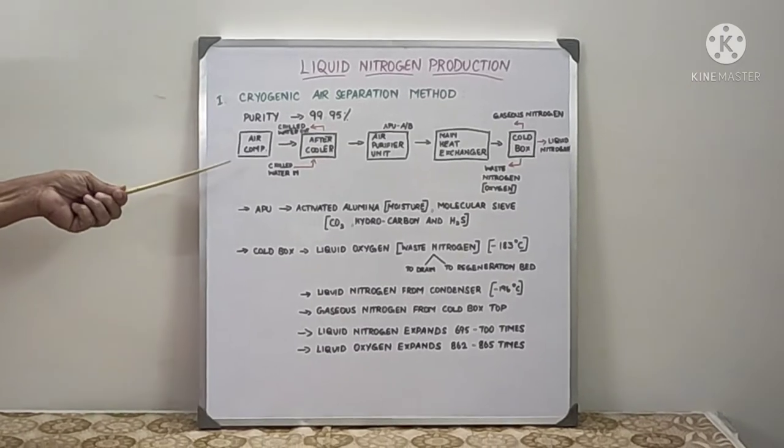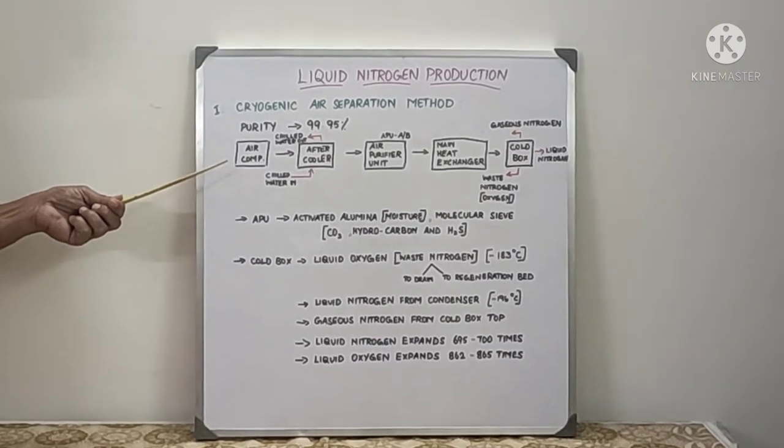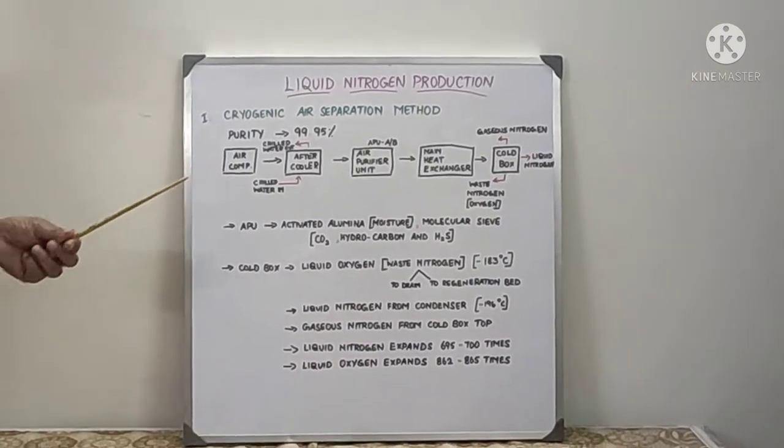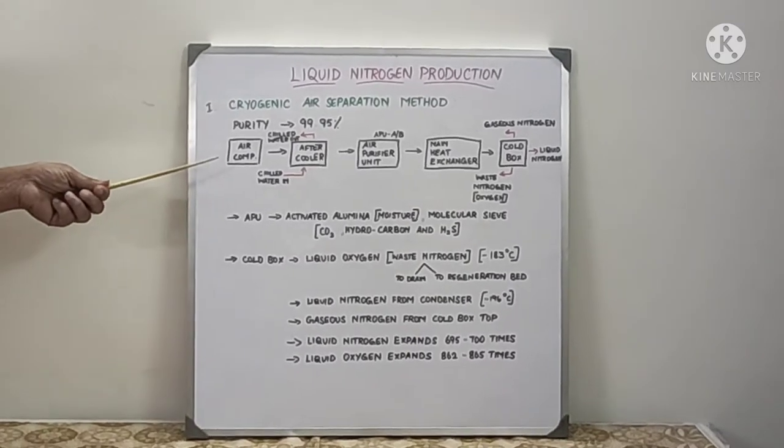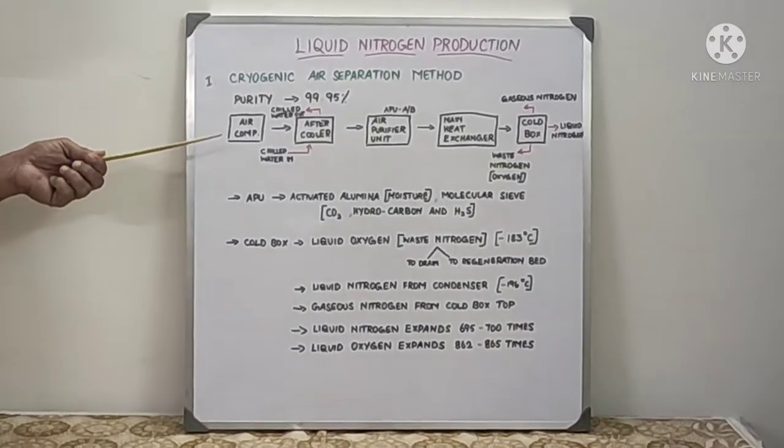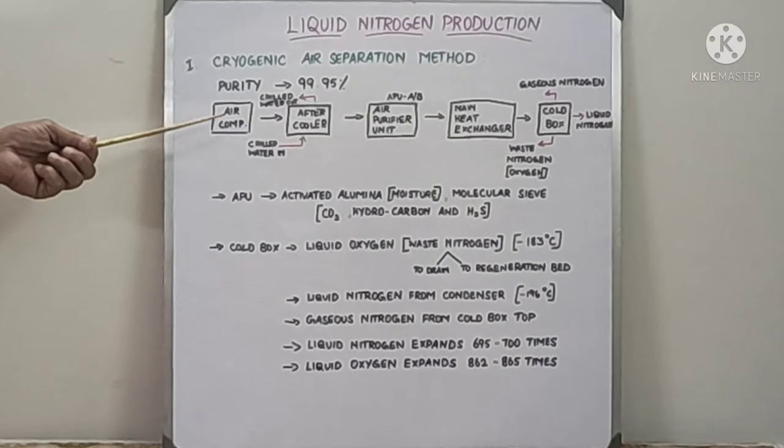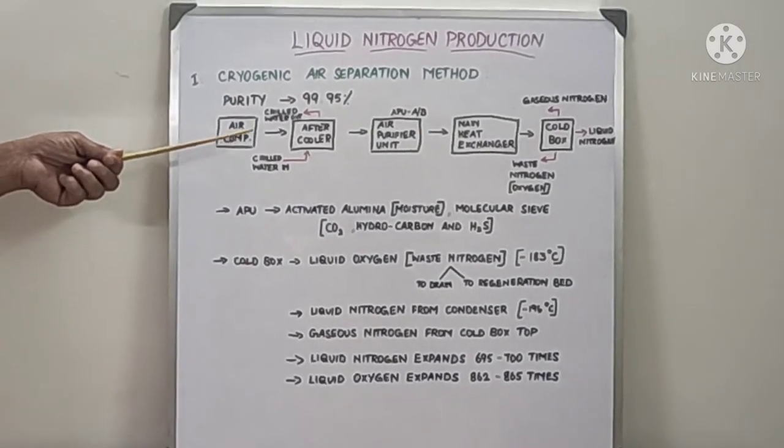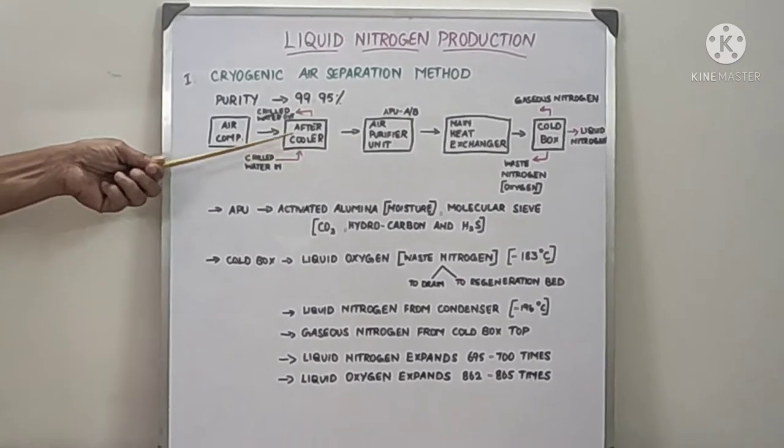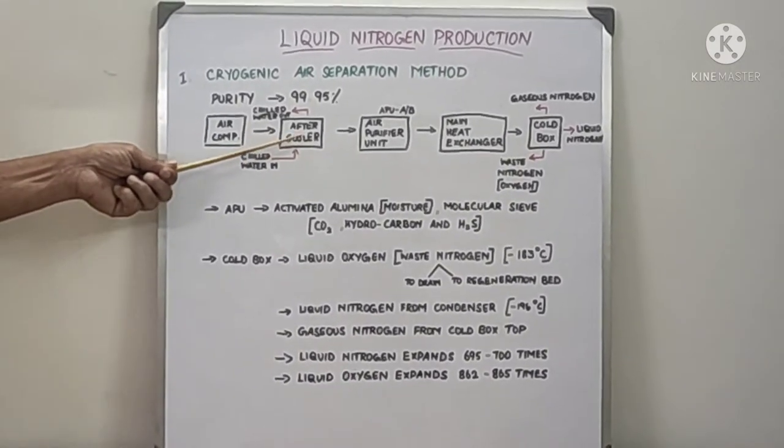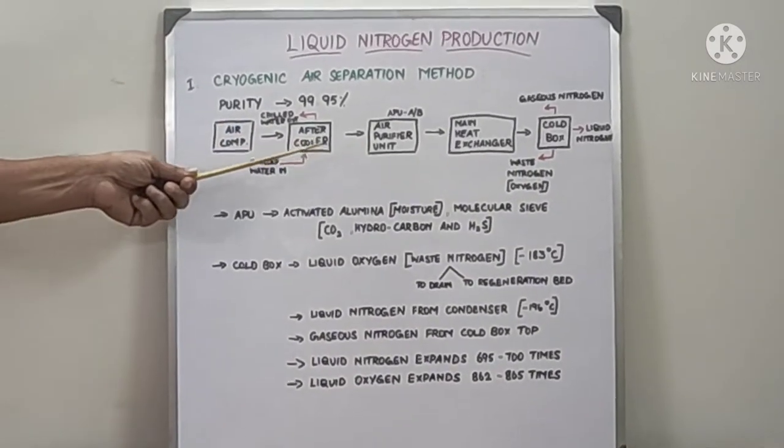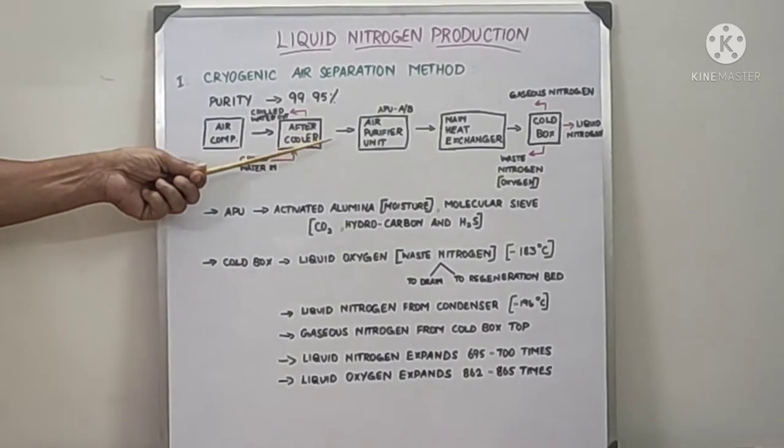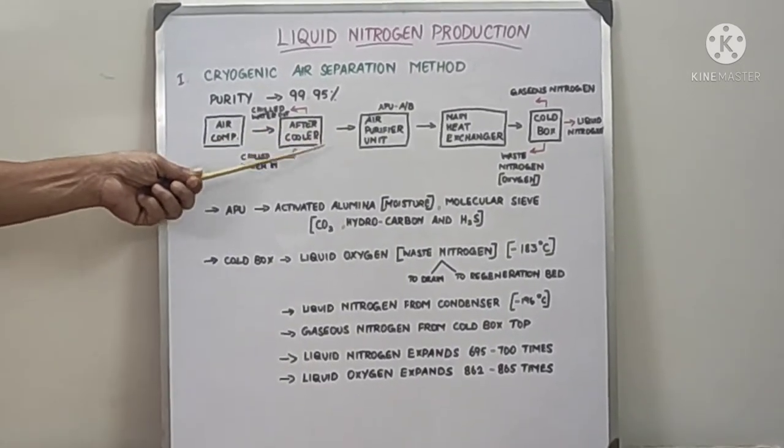Normally centrifugal compressors are used. We can use reciprocating compressor also. From the reciprocating compressor, air is compressed and cooled in the aftercooler. After the compressor, it comes to the chilled water cooler where the temperature will be reduced to around 15 to 20 degrees Celsius and moisture will be removed.